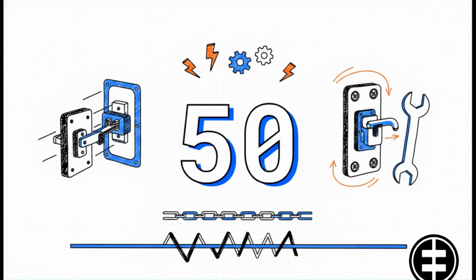And to guarantee long-term physical survival, it's not just about checking the wires. The standard actually demands 50 grueling operating cycles on things like draw-out racks and faceplate fixings. These are heavy, high-tension mechanical parts we're talking about. Operating them 50 times in a testing environment simply verifies that their correct mechanical operation won't degrade under the normal wear and tear of a facility's routine maintenance schedule.